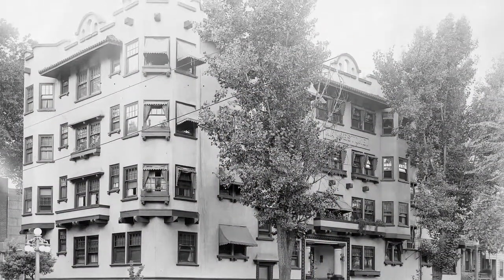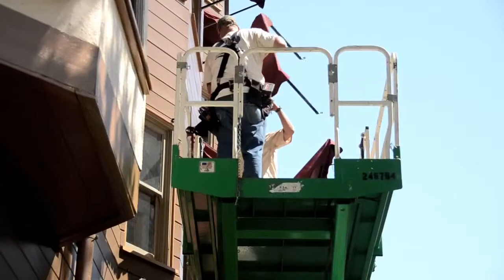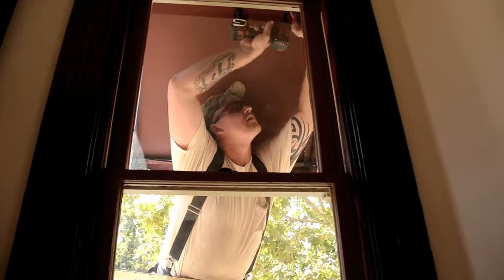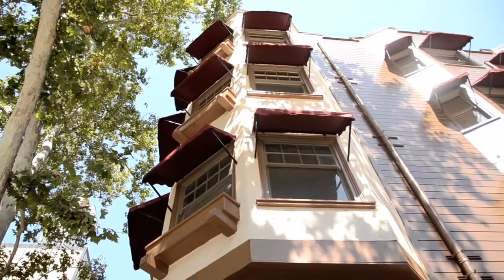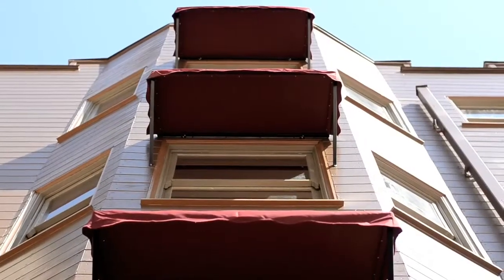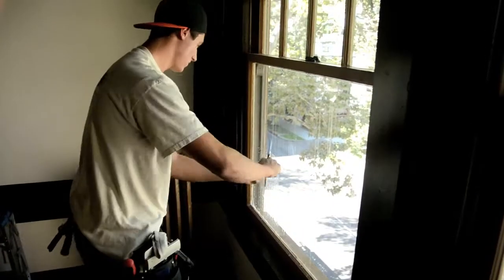One of the things we had to work around was the windows. The historical character of the building dictated that you couldn't do much with the windows, so what we came up with were awnings. That's what people used to do to cut heat gain into their homes and businesses — a very attractive red awning that fit really well with the building scheme. They were placed on the most important locations, the south and west windows, because that's where you get most of your heat gain. In addition, we also discovered window films. Window films have really advanced lately, and we put window film on all the east, south, and west windows, because those east windows make a huge impact — window films cut about 50% of the heat gain.